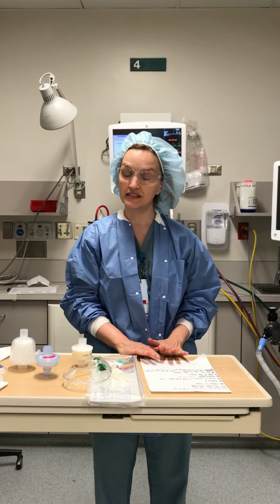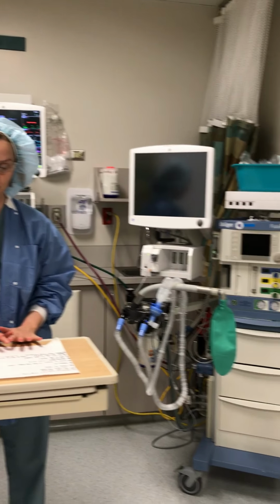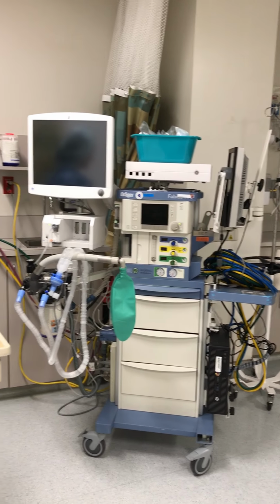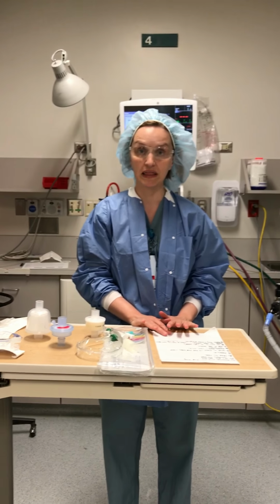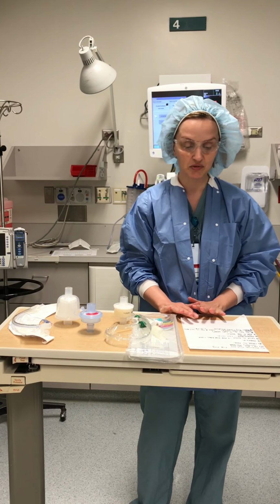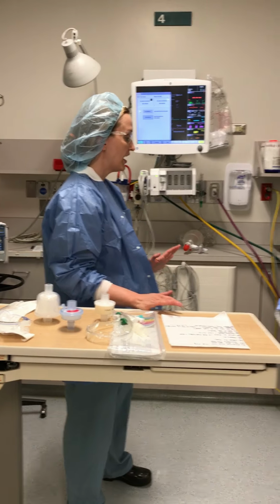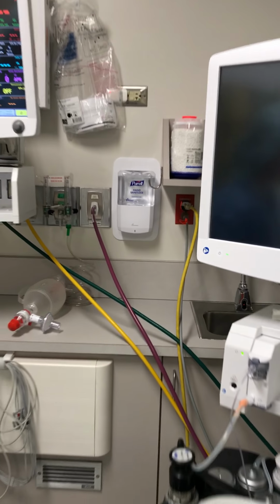Alright, so now I want to show you guys how to set up one of our anesthesia machines to be used for an ICU patient, because there are some notable differences from what we would normally do in the operating room. So we'll start with really basic stuff. We want the anesthesia machine plugged into one of the red wall outlets so that there's emergency power supply in case of a failure. So ensure that you're actually plugged into a red outlet wherever this workstation is.